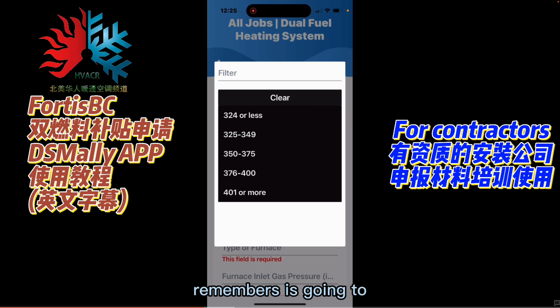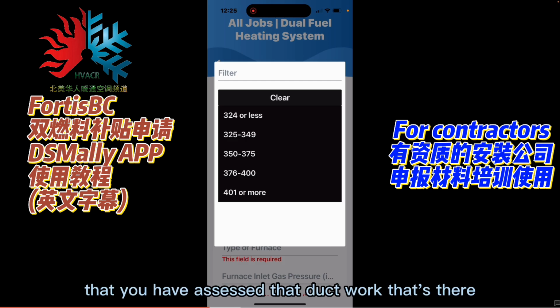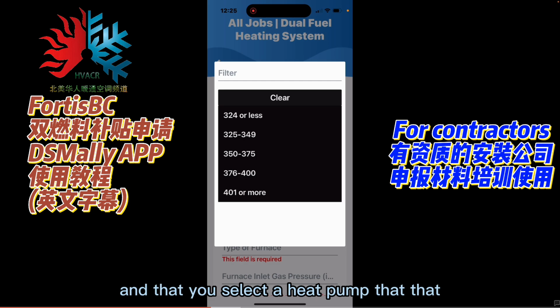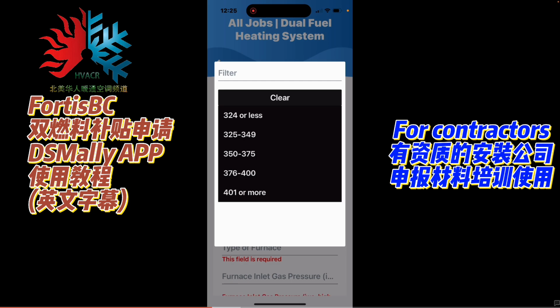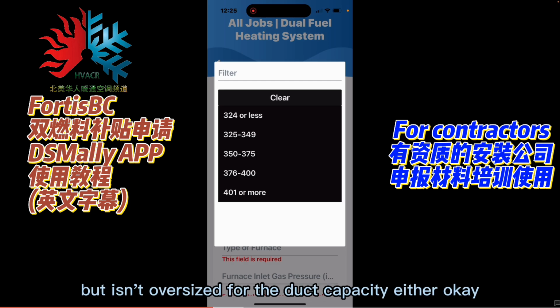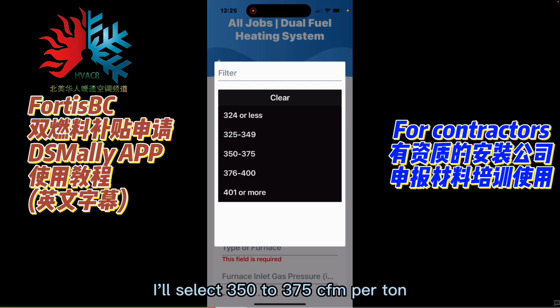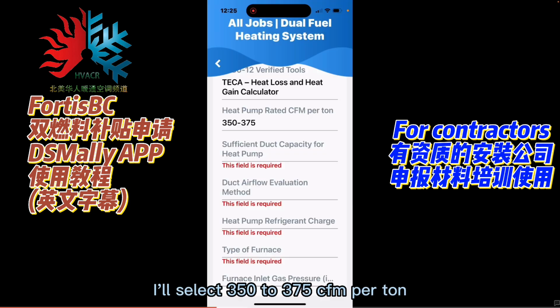The heat pump, remember, has a greater appetite for air than the furnace that you're taking out because it has a lower temperature rise. So we just want to make sure that you have assessed the ductwork that's there and that you select a heat pump that certainly isn't oversized for the loads, but isn't oversized for the duct capacity either, okay? I'll select 350 to 375 CFM per ton.